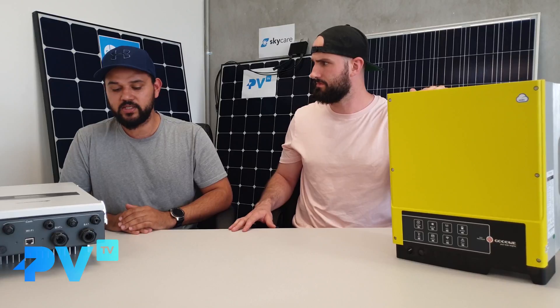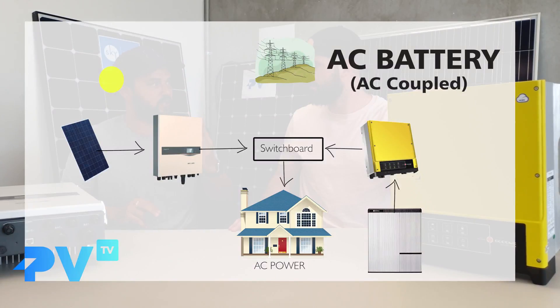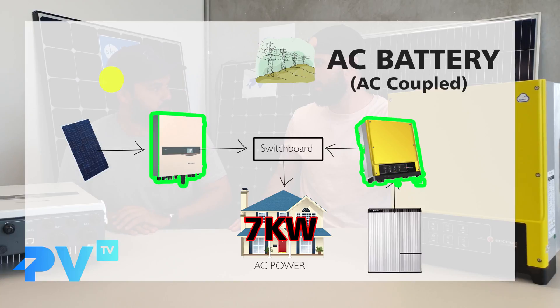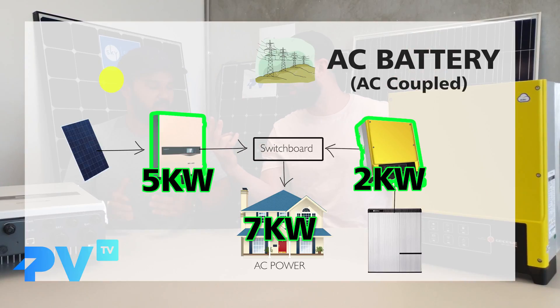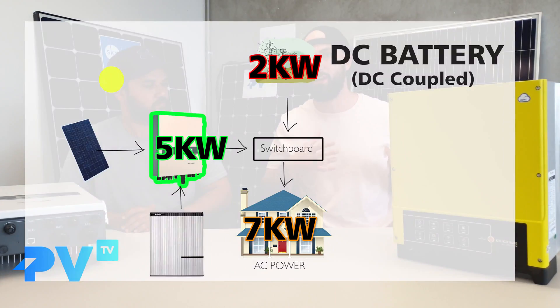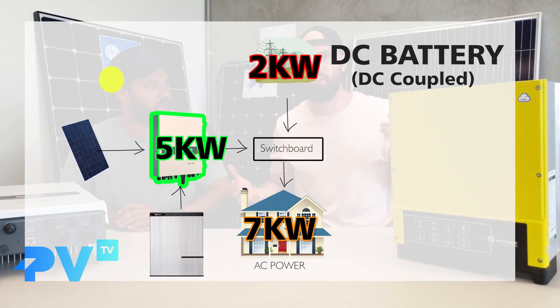The second reason is power output. With an AC battery you've essentially got two inverters: your solar inverter handling the solar panels and a separate battery inverter. So if the house needed seven kilowatts — say you turn on the oven and the kettle — it could take five kilowatts from the solar and two from the battery inverter. You get more output capacity from having an AC coupled battery. Most people won't need more than five kilowatts at a time, and a DC battery with solar in one unit can still output five kilowatts on average, which is plenty.